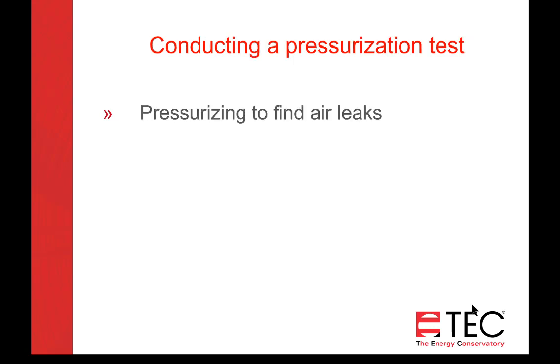Conducting a pressurization test, you might want to do a pressurization test to find air leaks. If you have a smoke puffer, it's easier to see the smoke travel from the smoke puffer to a leak. It kind of all flows towards the leak, than if you're depressurizing, the air is blowing in through the leak and the smoke kind of scatters and it's harder to find exactly where it is.